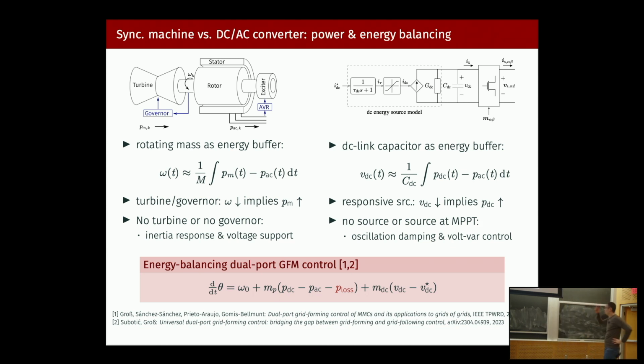What's a bit annoying though is that to do this you would need to know the losses of the inverter, which you typically don't. But you can write it like this, where you basically see that the time derivative of the DC voltage is nothing but the difference between the power that comes from here and the power that goes out here. This you don't want to implement in practice because it has this d/dt of the DC voltage, which is a noisy signal.